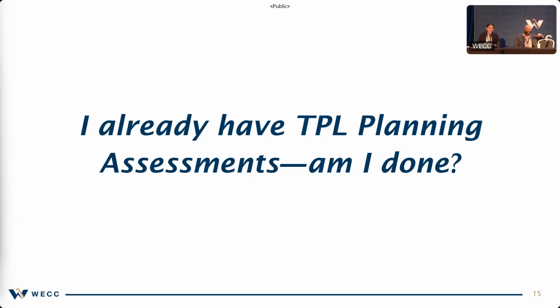Jamie? Yeah, I have thoughts. Well, it starts with the model. TPL has a specific time and place, a specific purpose. It goes through looking at the model you have for your area, and you're running contingency analysis—taking out individual facilities at a time, whole transmission lines, or transformers. There's a variety of contingencies you're running, determining whether your system can survive each of these. This is long-term planning. It allows you to determine whether you need to build additional substations or add reactive devices. There's a slew of corrective action plans, but the first aspect is: what's my risk if something happens in a normal situation where I have a disconnect or contingency?